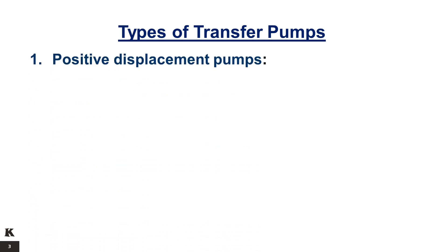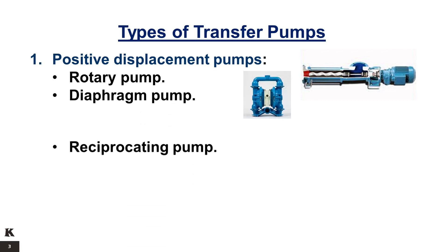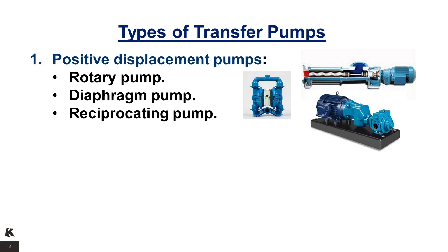Types of transfer pumps. 1. Positive displacement pumps. Positive displacement pumps employ a moving piston and either a plunger, diaphragm, or rotor to move a fixed volume of liquid per revolution of the pump. It includes rotary or screw pump, diaphragm pump, and reciprocating pump. Positive displacement pumps are generally used for fluids with a relatively high viscosity. They can be used where high accuracy is required, for example in metering, or where high pressure is required, for example high pressure washing.